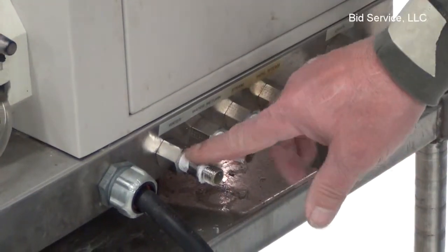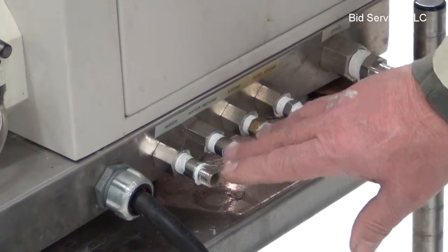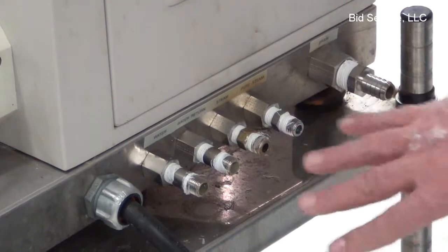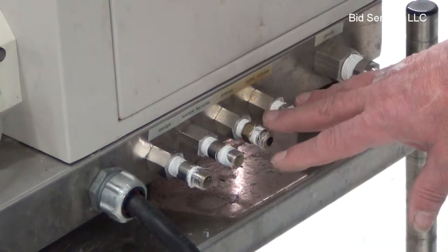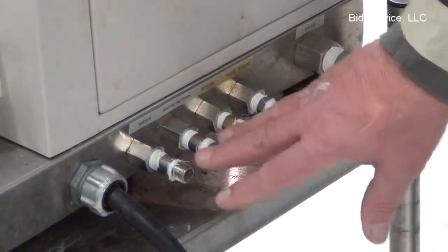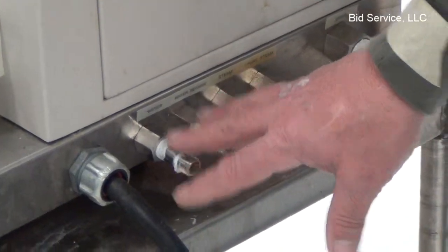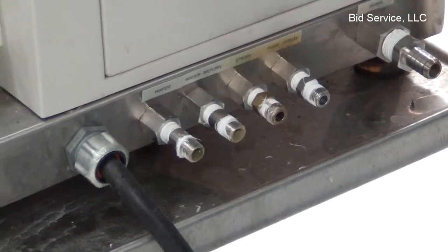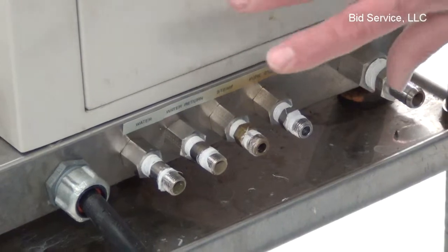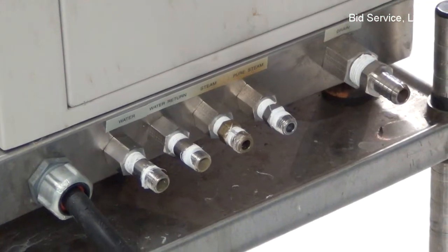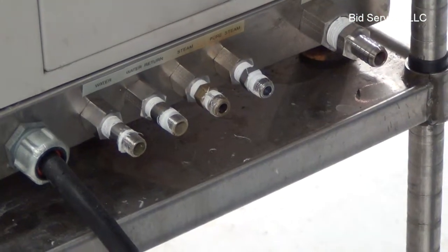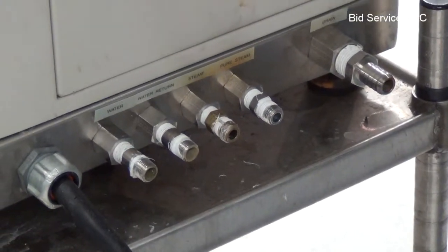These were all connected. I've run this, and they do not have steam capability, so I pressurized it there to make sure that it was okay. Did run the water, but I ran into a chiller. A chiller is not enough to do the proper job. You need to have this set up to actual a flow of water, like from a sink or something, unless you've got a really large chiller.